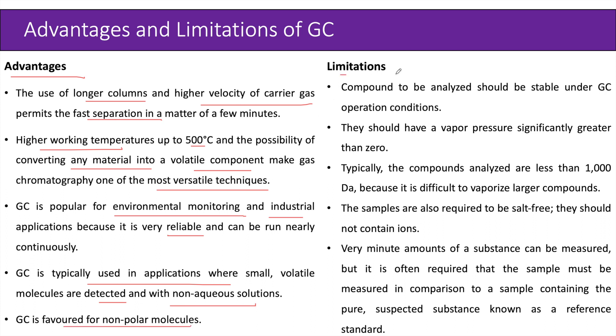Limitations include that compounds to be analyzed must be stable under GC operating conditions. They should have a vapor pressure significantly greater than zero. Typically, compounds analyzed are less than 1000 daltons because larger compounds are difficult to vaporize. Samples must be salt-free and should not contain ions. Very minute amounts can be measured, but often the sample must be compared to a reference standard containing the pure suspected substance.